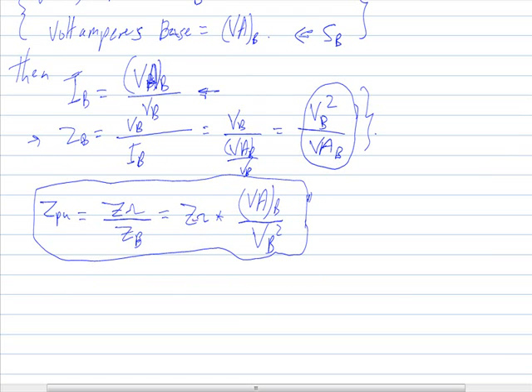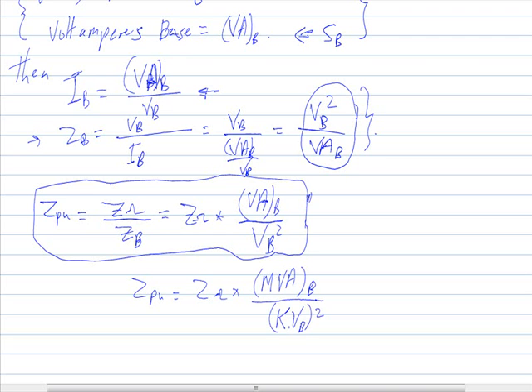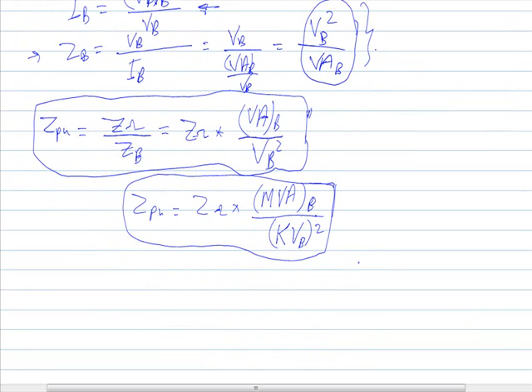Sometimes, instead of using the base quantities directly, we express the per unit impedance of any component in the power system as the actual impedance multiplied by the mega volt-ampere base divided by the kilovolt base squared. So the voltage is taken in kilovolts and the apparent power is taken in mega volt-amperes. This is equation number one, used in power system analysis for single-phase circuits.